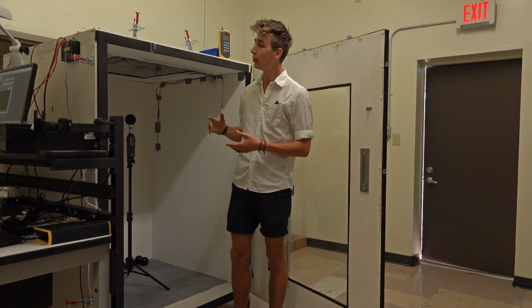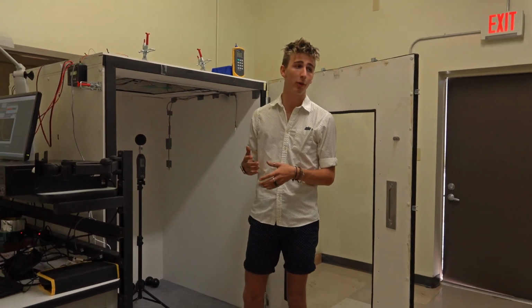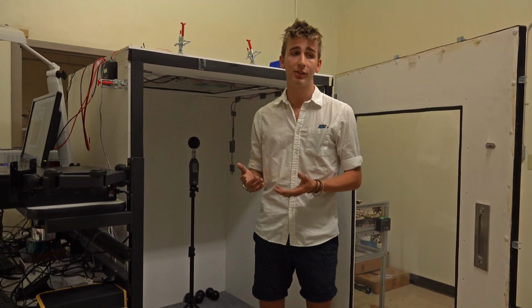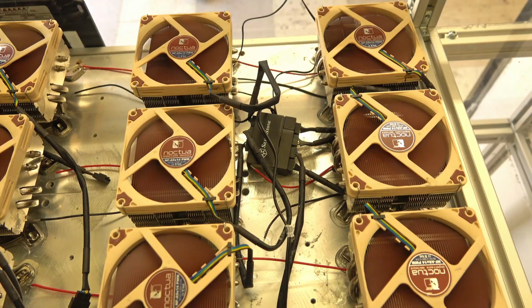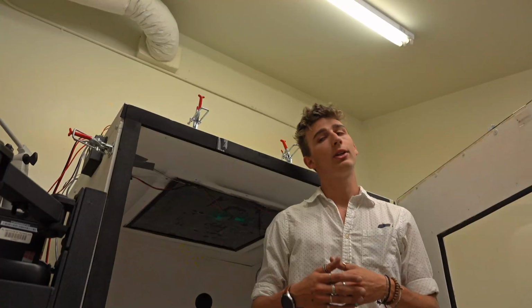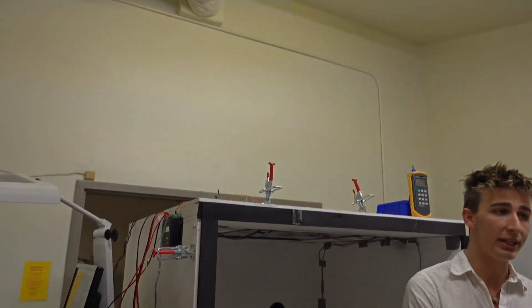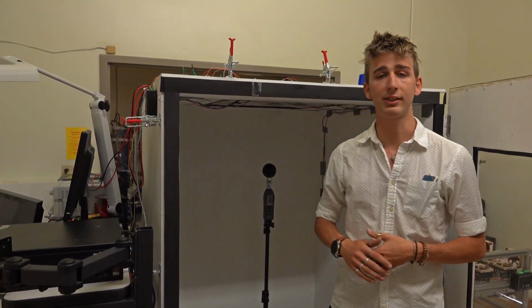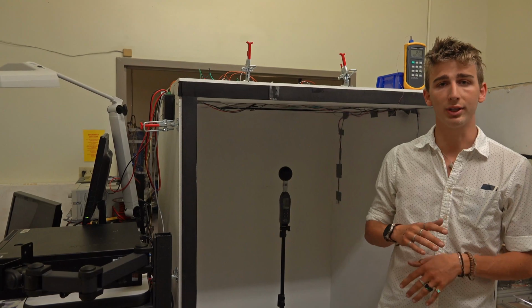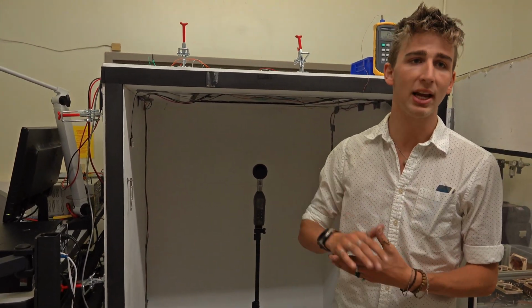As stated previously, we are going to be using thermoelectric modules, which have a lot of benefits over the refrigerant cycle. One of them is that they are solid state. There are no moving parts. It's simply electrical current passing through a semiconductor, and there's nothing to move. The system can be completely modular. You can have one system on in a certain part of a building and another completely off and not using any energy. Another benefit is there's no use of refrigerant. So this process is very safe for the environment, and there are no harmful chemicals being dumped after the fact.